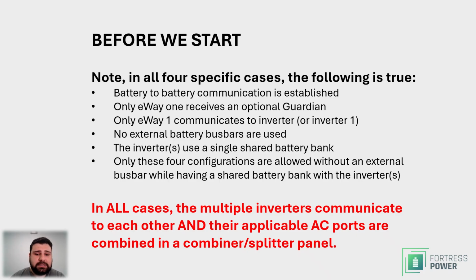The inverters use a single shared battery bank. Yes, we're not grouping the batteries per inverter. We are creating one shared battery bank. Only these 4 configurations are allowed without an external bus bar while having a shared battery bank with the inverters.